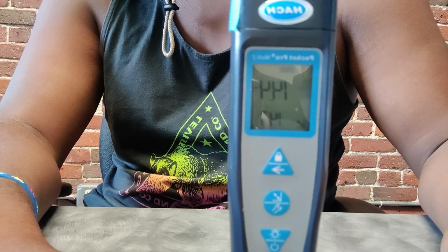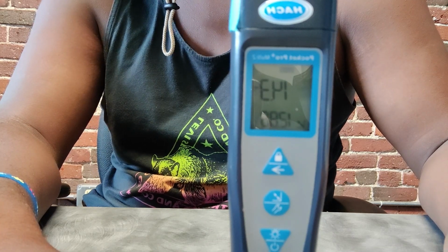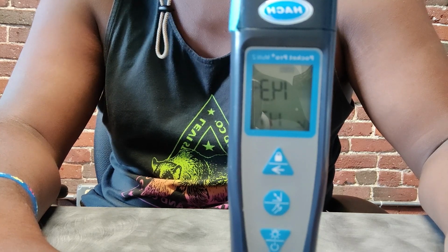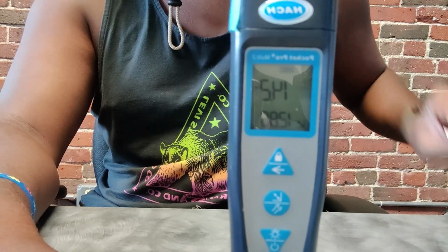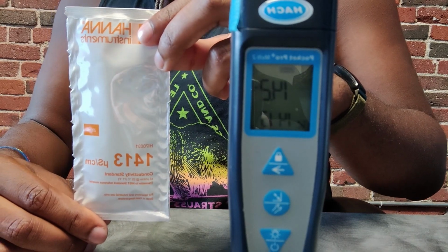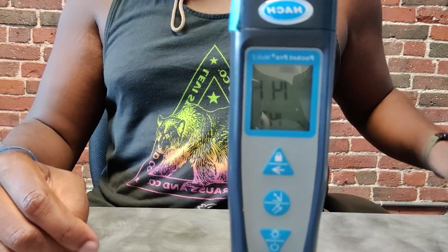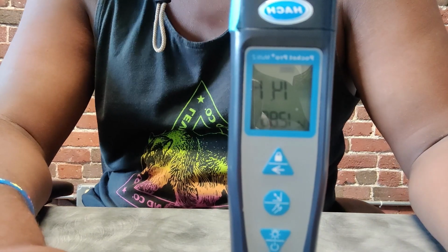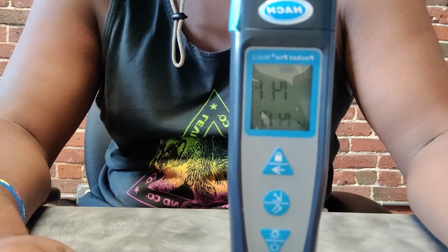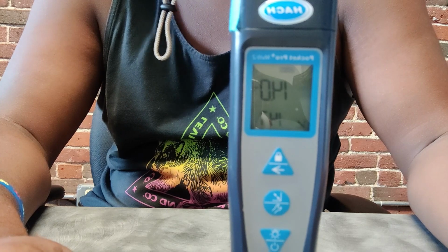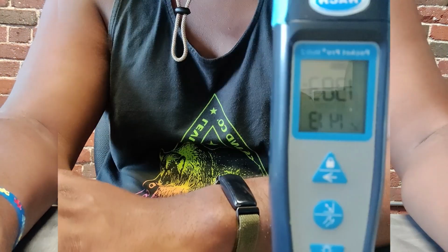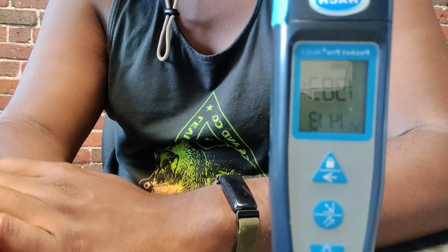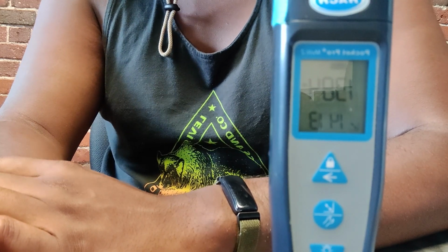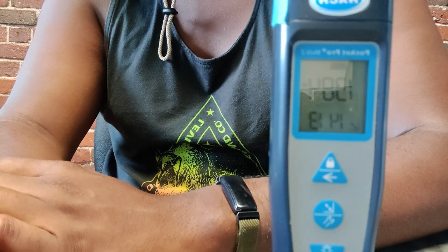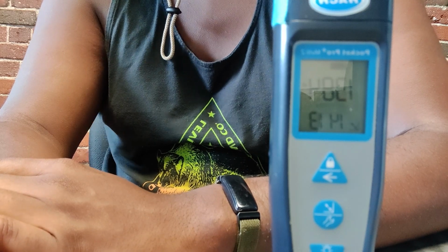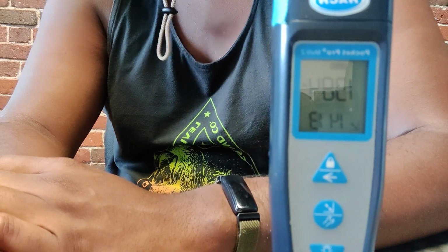There are 3 different systems of measure. We are using the system of measure that stipulates 1413 microsiemens per centimeter conductivity standard, which is the orange packet. Just open and pour the fluid from the orange packet, as you had before, into the cup, and the Hach will automatically catch the conductivity type and adjust accordingly. Let the numbers on the top row settle. If the first 3 numbers are stable, but the last number may be flickering between 2 different readings or is moving very slowly after 30 seconds, it's fine to accept that reading.